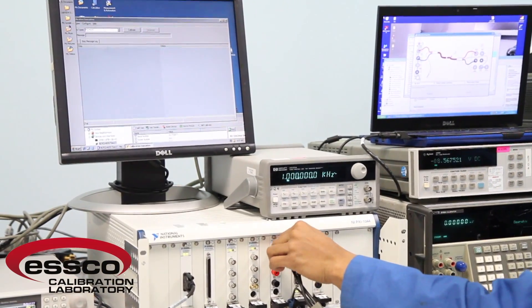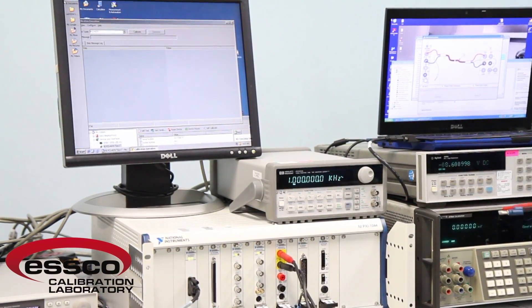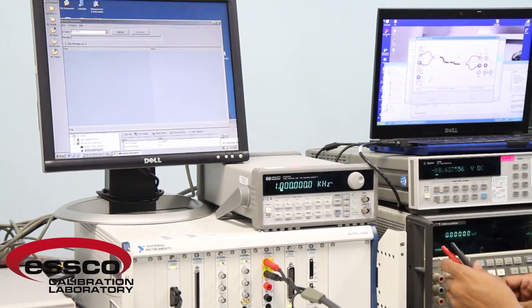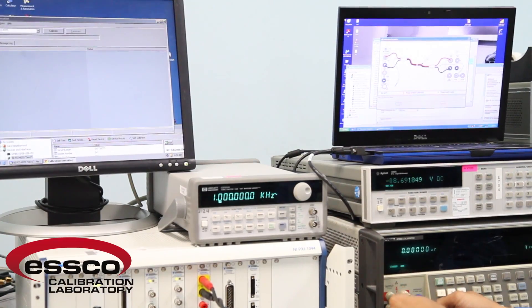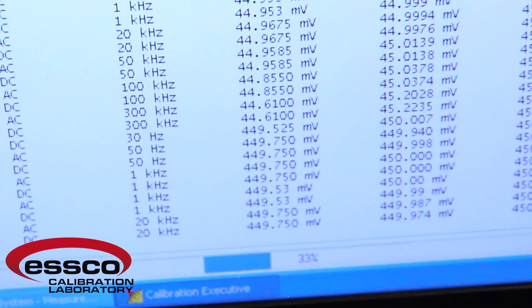Once the technician identifies the model number for the unit being calibrated, the software will prompt the technician with a list of acceptable standards and the proper way to connect the instrument. The software then executes the proper program, controlling both the unit under test and the standard being used.